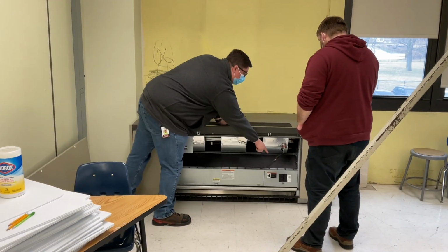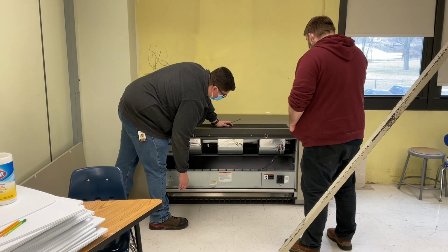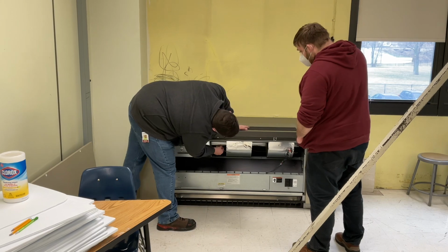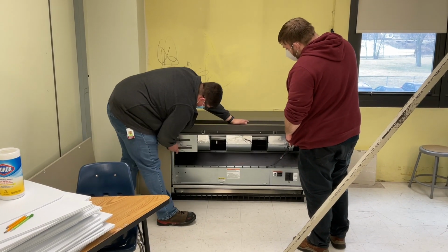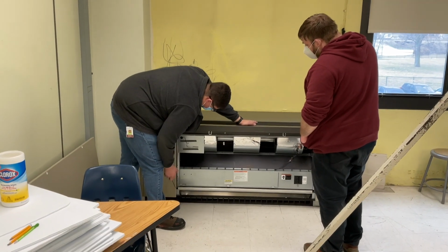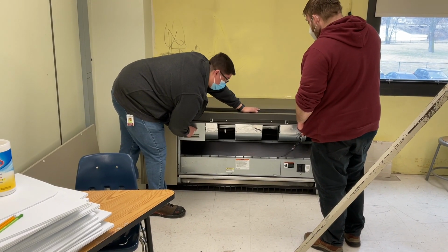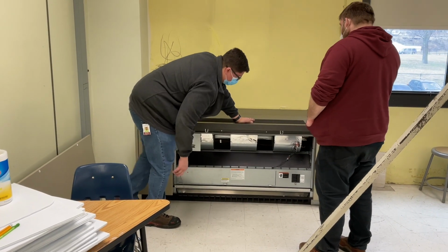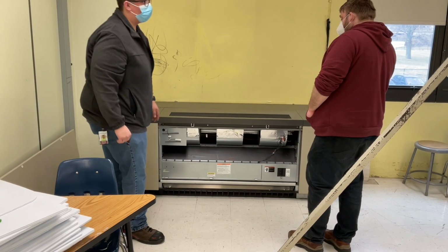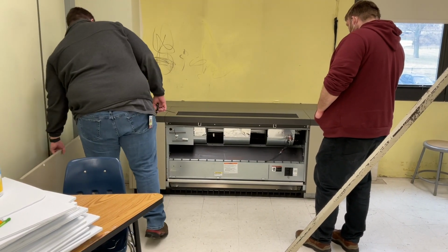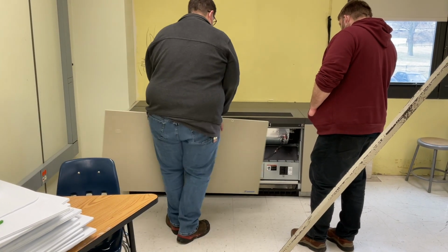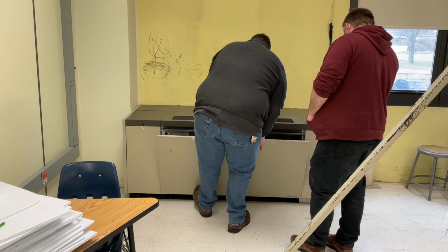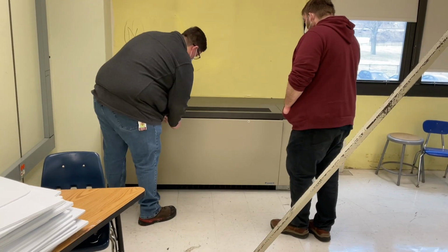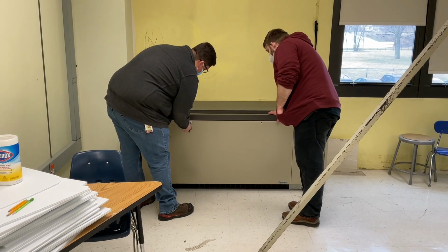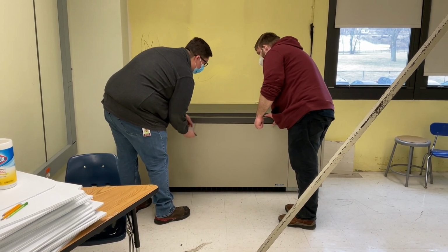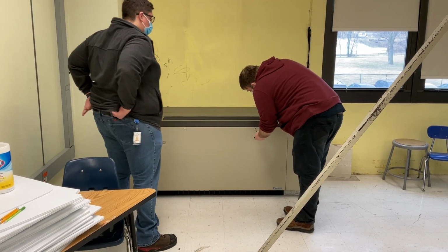All right, so there's that disconnect. If you were to cut that, that would cut off the controls to us. You can see our DATs here. It's all wired in through here. And then this is our return air temp sensor. So that pulls it up through here. That's why this might read a little cold sometimes. That's pretty much it. And then down in there you can see that mixed air damper. You'll need to open up that so you can access it. Just got that one more side I want to open up.